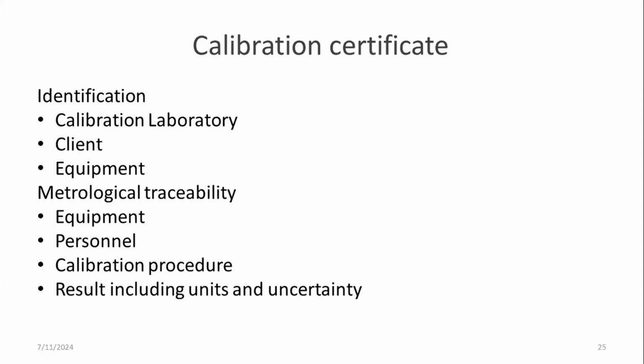Like I said earlier, each certificate is for a particular equipment, not sampling, not batches. So if there are 100 pipettes, each pipette must have its own certificate. And then the second thing that we have to look out for is the metrological traceability. And when we talk of metrological traceability, we are looking at the equipment that was used to calibrate the client's equipment, because it is the one that is tracing the SI unit to the national standards.